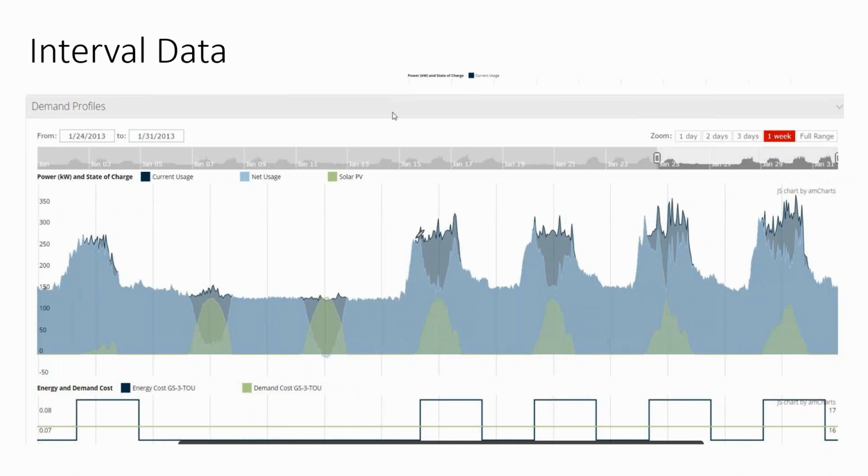If this commercial facility had access to real-time electricity pricing, then they would see those savings roll off their bill, because real-time electricity pricing is updated every 15 minutes along with your building interval data. But just like a residential consumer has a simplified electric bill, not billed for demand, just billed for energy, a commercial facility has a simplified electric bill. They're not being billed for their real-time electricity usage. They're just being billed for their maximum demand and the amount of energy they use.